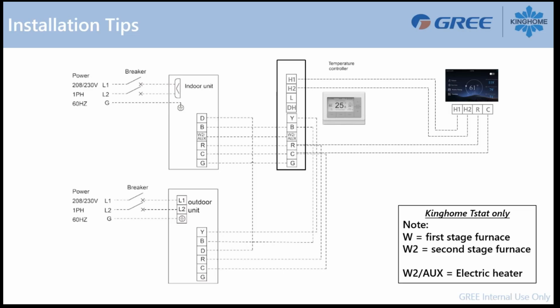But if you are using the KingHome thermostat, this is a big difference I want to point out: we have a W and a W2 slash aux. If we're using the air handler, we will have only W2 aux connected from the thermostat to power up the duct heater. And that's it. So W will not be in use with the KingHome thermostat, only W2 slash aux.